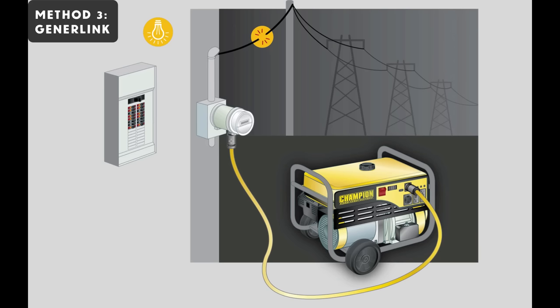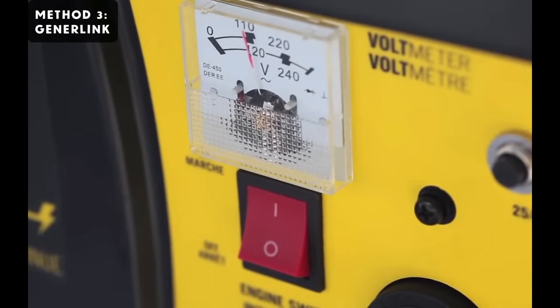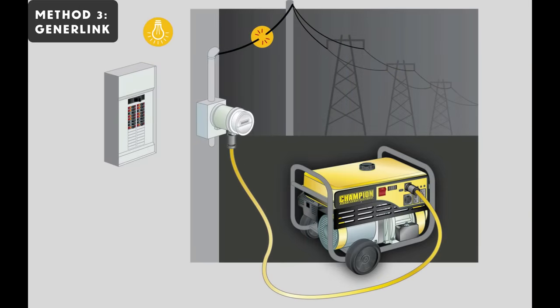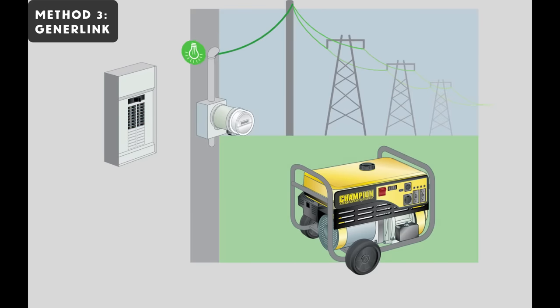Now, if an overload should happen, that's not that big of a deal, because every generator has a built-in breaker that's going to protect the generator from trying to produce more power than it safely can. So, if you overload the system, all that's going to happen is that you have to go out and reset the breaker on the generator. With things the way they are now, as you see them, this system can continue to power your home indefinitely. And when the power comes back on again, you just simply disconnect everything. You shut the generator off, you remove the cable, and you return the breakers in the panel to their former position, and it's business as usual until you get another power failure.